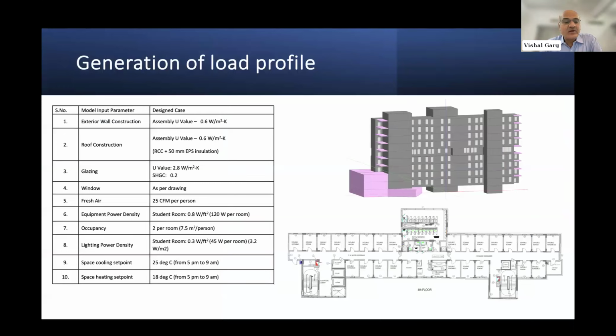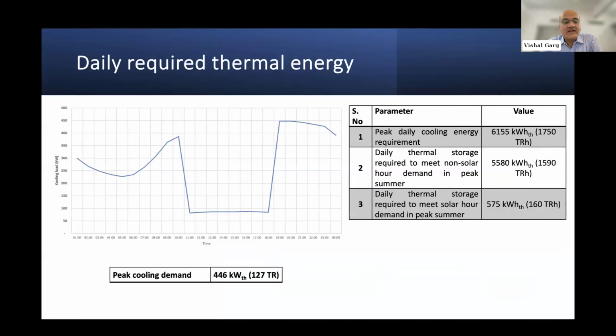We simulated the hostel building as per the construction materials and as per the as-built drawing. And then we found that this is how the cooling load changes throughout the day. The peak load comes at around 7 o'clock, 7:30, when students are back into the hostel and ACs are on. During the daytime, they are in the classrooms or the labs, so the air conditioning utilization is less. So what we found that the peak requirement was 127 tons, and the total energy consumption on a peak day in a year would be 1750 ton hour.